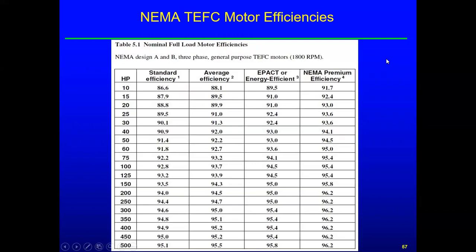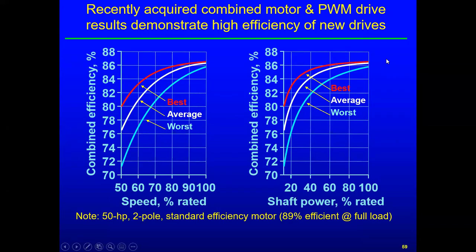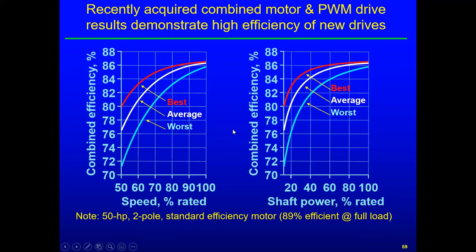Large motors today — premium to standard efficiency — run 94 to 96% efficiency. Replacing an oversized motor purely for efficiency reasons is probably not worth it since efficiency doesn't drop much with reduced load. Don Casada tested a 50-horsepower two-pole (3600 RPM synchronous) standard-efficiency motor at 89% full-load efficiency. The combined motor-VFD efficiency data for three different manufacturer drives shows that as you ramp back speed, combined efficiency falls somewhat, but this doesn't mean VFDs are a bad idea — you just need to be aware it's happening in the background.